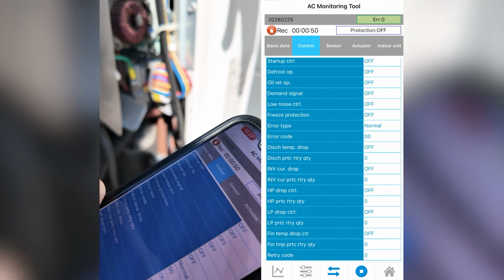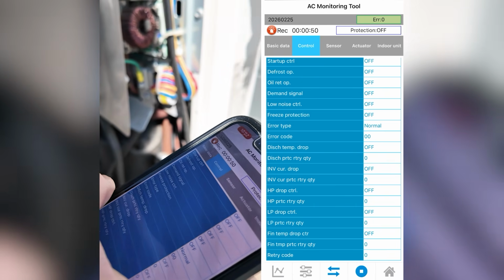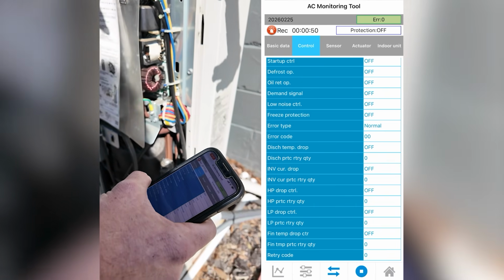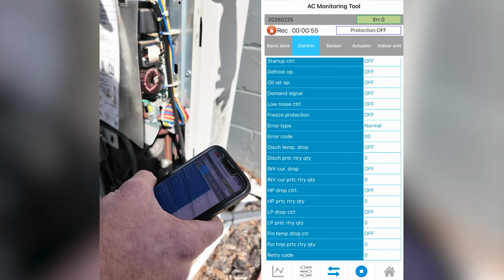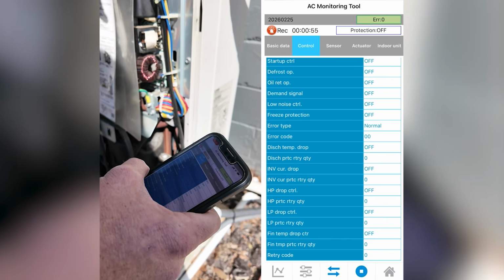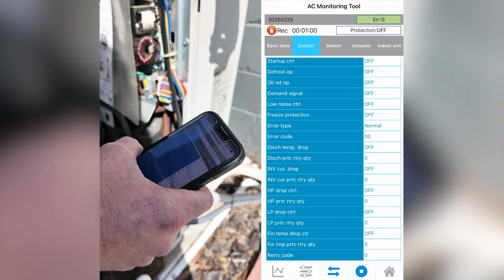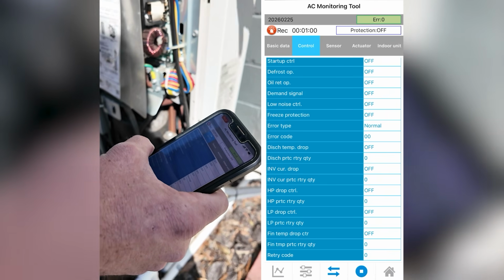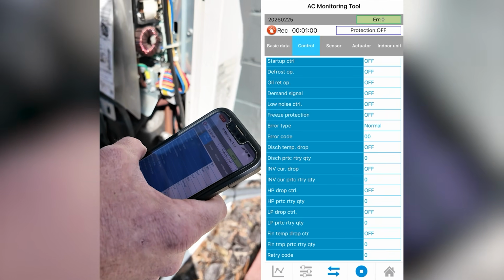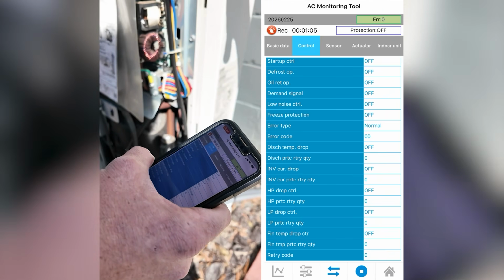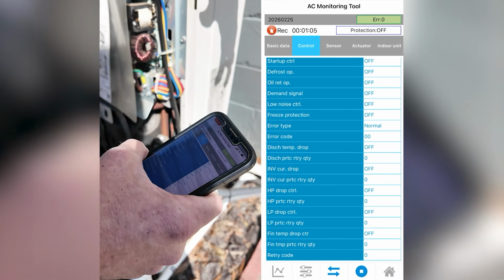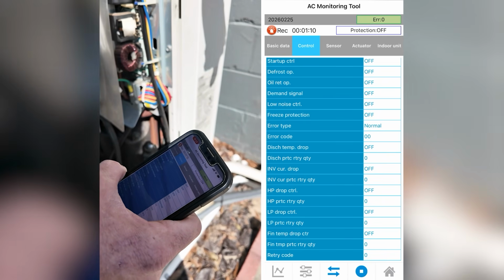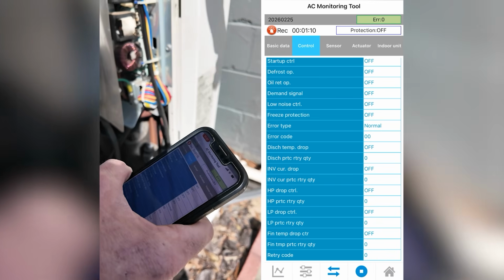Let's say this is something I would want to do if I've got a system that's doing something erratically, that isn't behaving the way it's supposed to, and I want to find the root cause, where I should go next after everything else doesn't make sense. There are no error codes, but it just doesn't run correctly, or it makes a ton of noise, or it does something at midnight. You want to get at least a good hour to 2 hours of runtime data on your phone while you're either manually testing the system by turning it into heat, then turning it into cool.